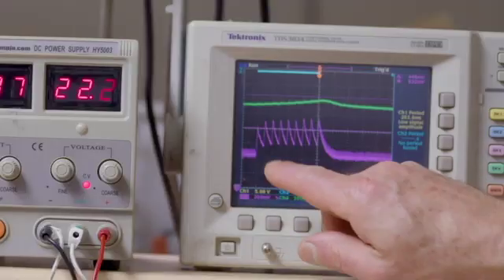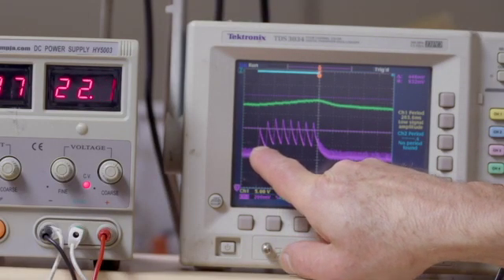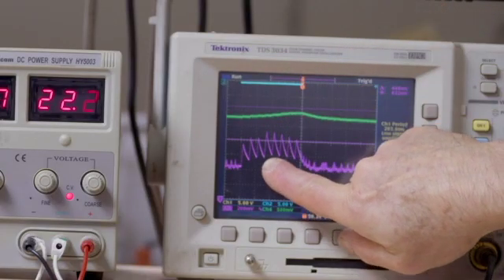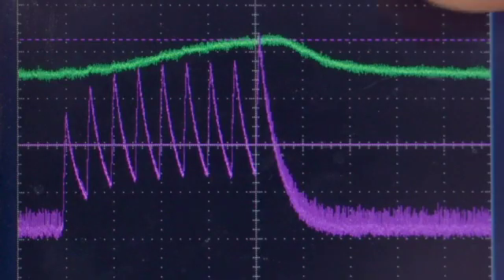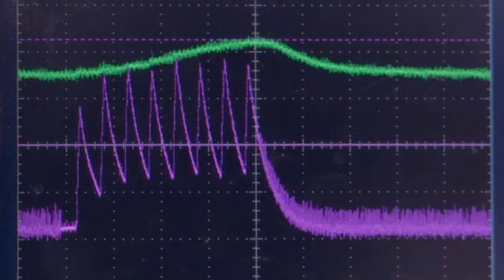You can hear the valve turning on and off about 5 times a second, feeding air into the calibration chamber. The pressure inside this chamber is shown in the purple waveform. When the valve opens, the chamber pressure jumps up. Then, while our valve is shut, this chamber pressure falls because air is going out to the patient. That pressure fall is the important bit because it tells us exactly what quantity of gas has gone out to the patient. Our patented electronics needs only to monitor the high and low pressure points to know the precise flow going to the patient on each cycle.